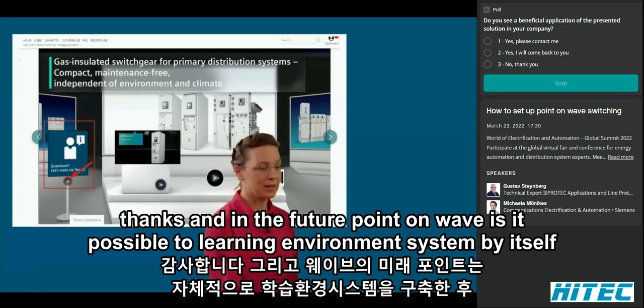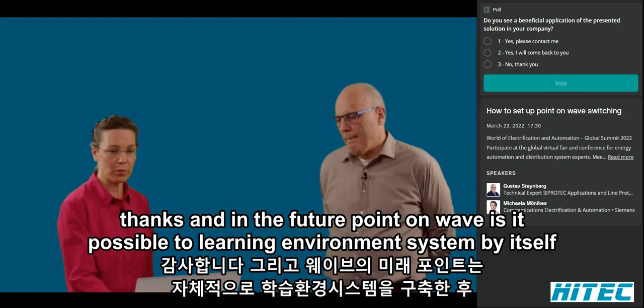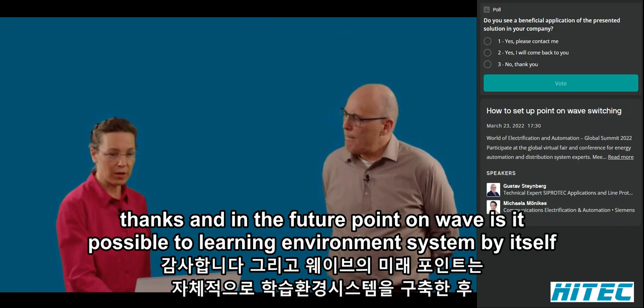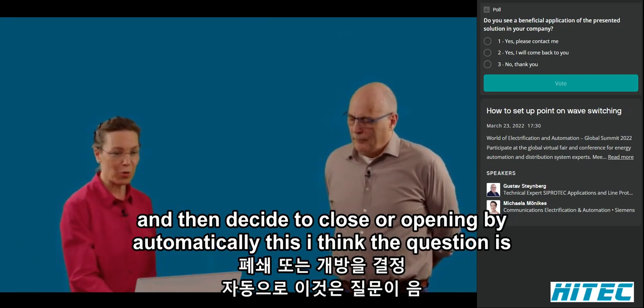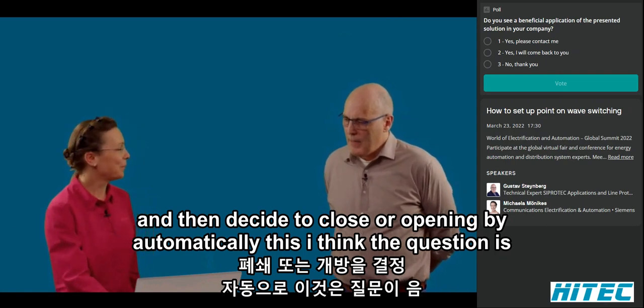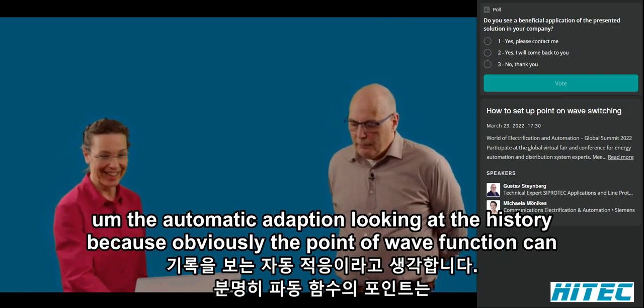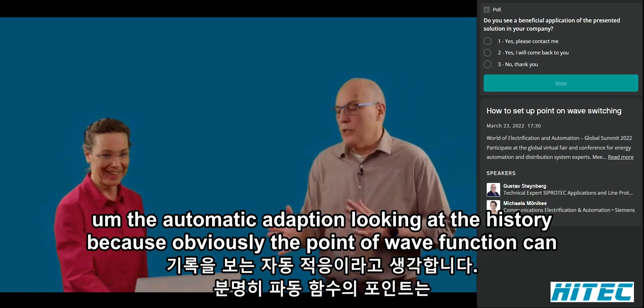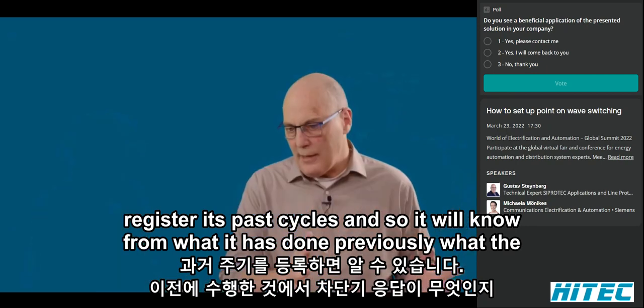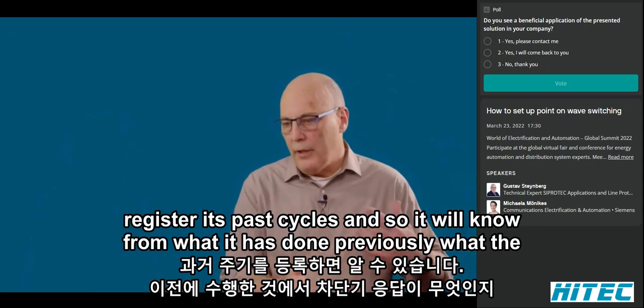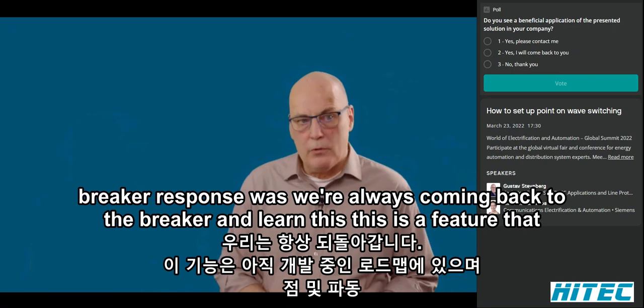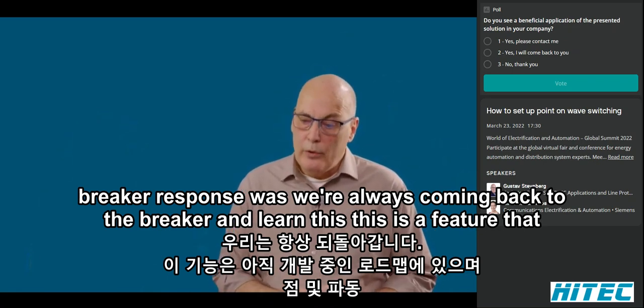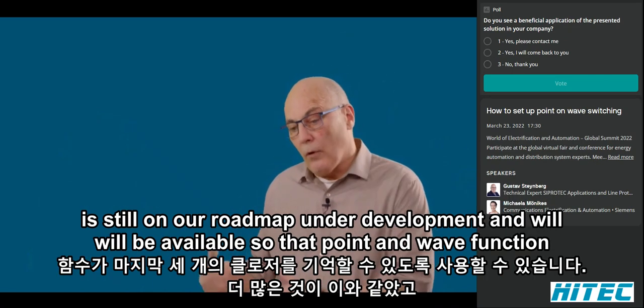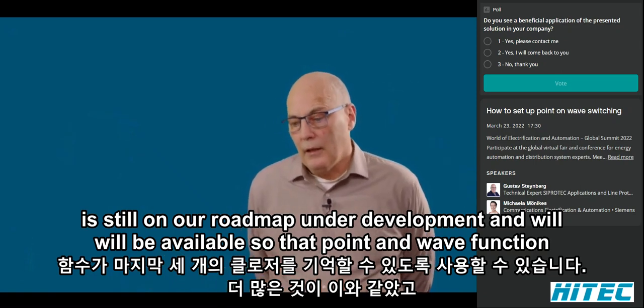Okay. Thanks. And in the future, with point-on-wave, is it possible for the system to learn the environment by itself and then decide to close or open automatically? I think the question is the automatic adaptation, looking at the history, because obviously the point-on-wave function can register its past cycles, and so it will know from what it has done previously what the breaker response was. We're always coming back to the breaker. And learn this. This is a feature that is still on our roadmap, under development, and will be available.